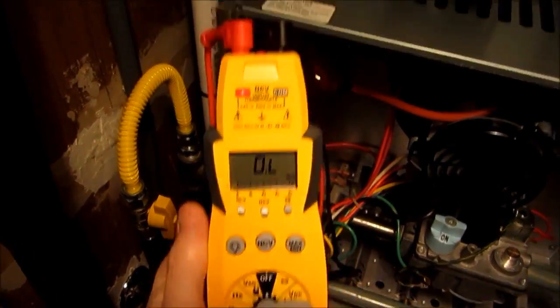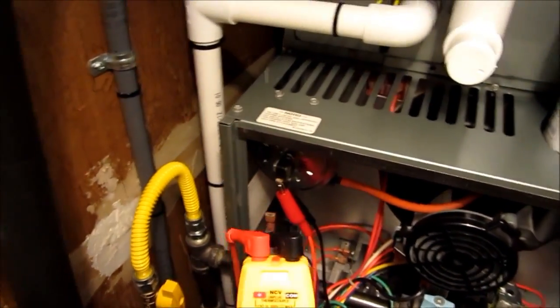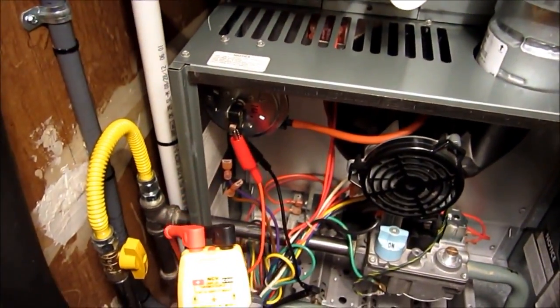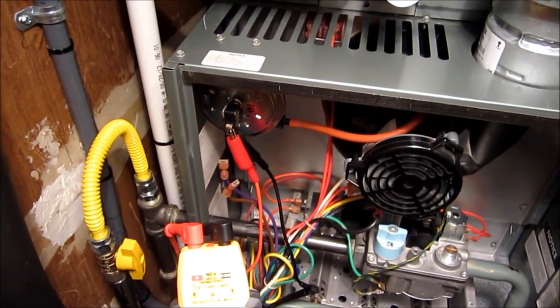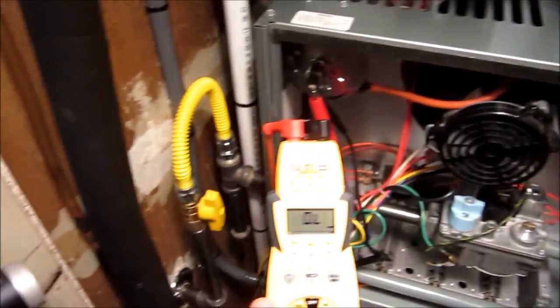Now, if you measure any resistance whatsoever, that pressure switch is shorted and needs to be replaced right out of the gate. If you read 0.1 or any resistance whatsoever. Okay, well, let's try another electrical test.